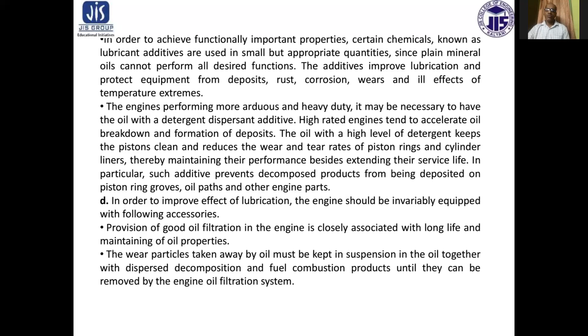Next, prior to engine startup, the main difficulty encountered is with engine lubrication, as fully stable oil circulation is not being established. As a good practice, priming pumps are used essentially on large engines to ensure adequate flow of lubricant is established before start up. Arrangement for preheating of lubricating oil up to 60 to 70 degrees centigrade before startup can reduce the warm-up period for the engine.